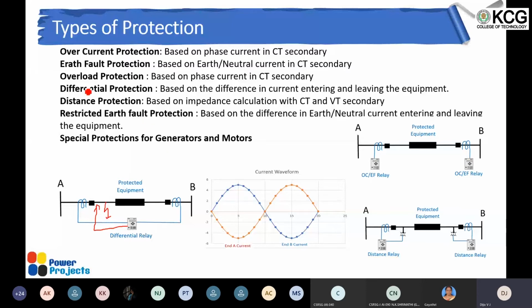Another protection is overload protection, generally used for motors and other equipment, even for cables, and sometimes transformers. Basically it calculates the loading and tries to calculate the temperature of the protected equipment from the current. We know that the temperature rise is proportional to the losses, and the losses are I squared R. Based on that, the relay calculates the operating temperature of that equipment and decides on tripping. Again, it takes the CT values, so you can assume the installation will be something similar: the relay gets a connection from the CT.